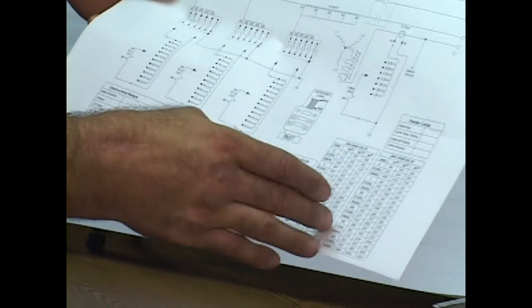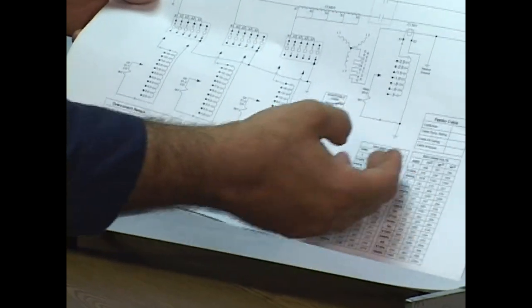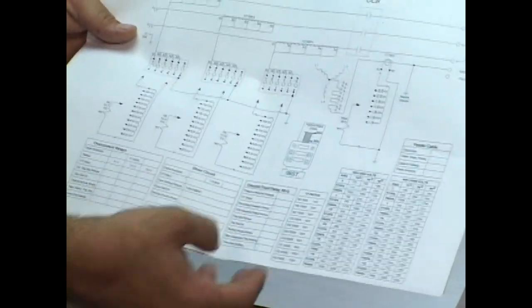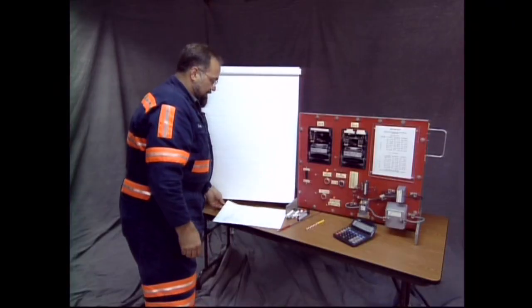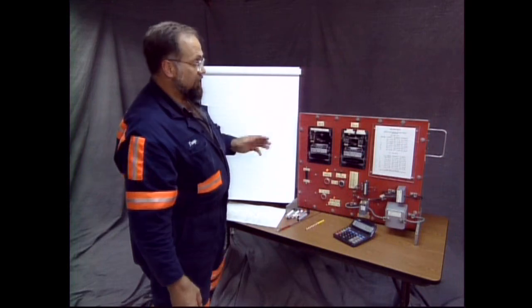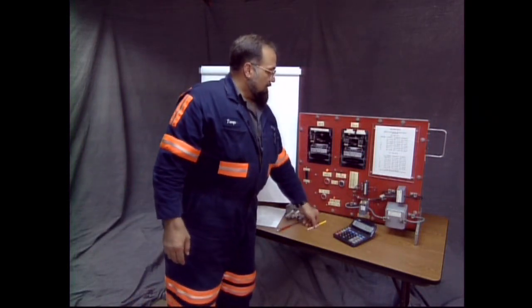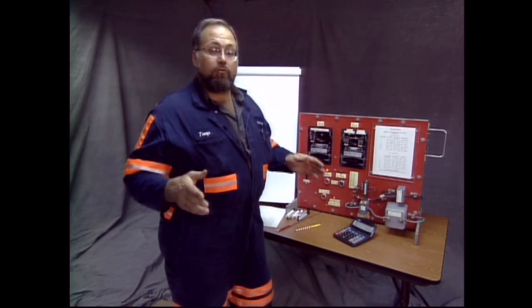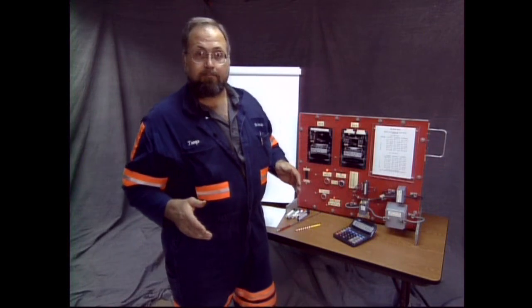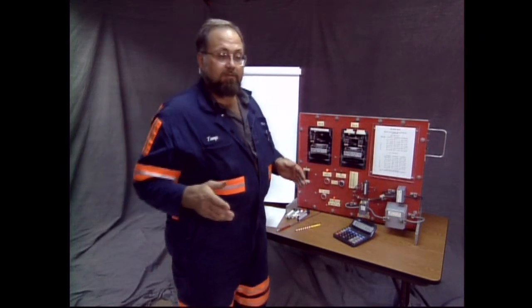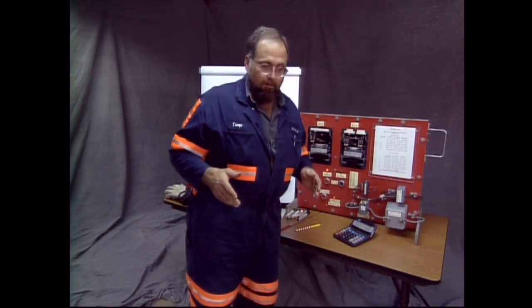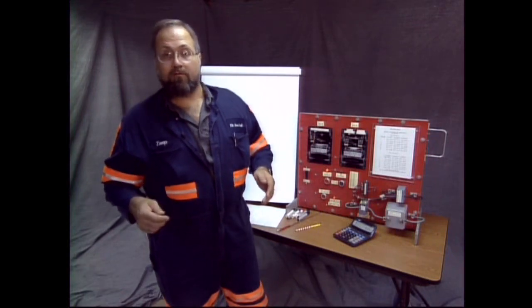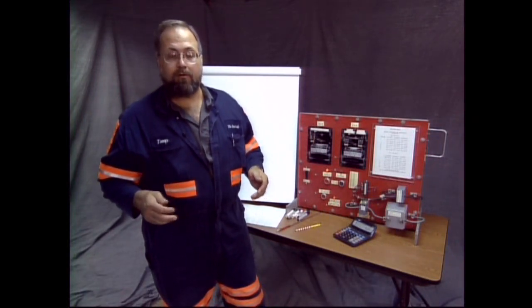They'll give you a cable size to figure. You use the chart. Here's all the ampacities of the cables. Here's the CT ratios, and you just fill in the blanks. That's a really, really simple form. It's much easier now than it was. Okay, to do a monthly check, if part of your test involves to illustrate a monthly examination of a high voltage circuit breaker, this will be what you did.